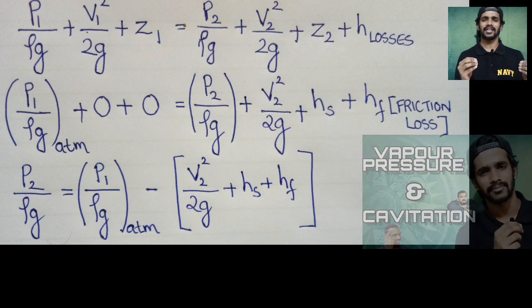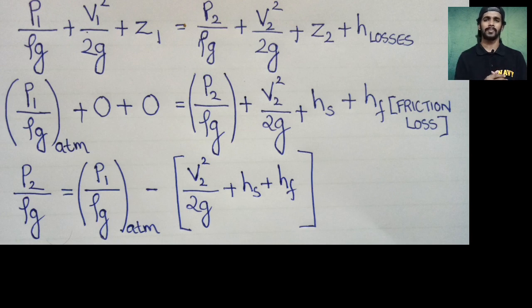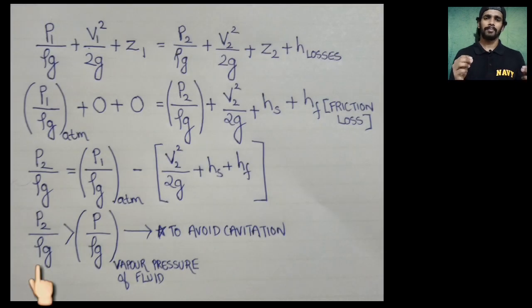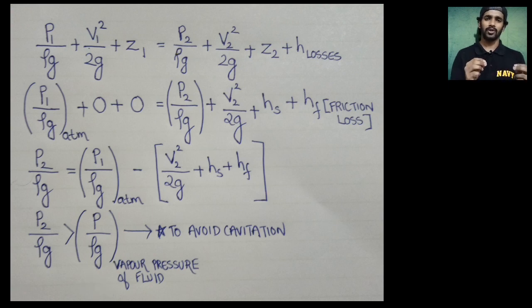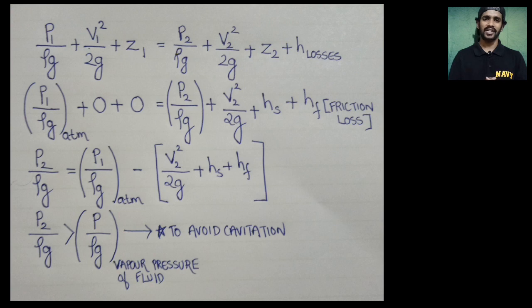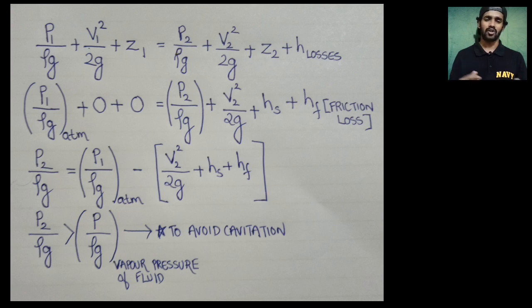As discussed in our cavitation video, the pressure at the eye of the impeller must be less than atmospheric pressure, but it should not be so low that it becomes less than the vapor pressure of the fluid — because if that happens, cavitation will occur. We modify the equation: P2/ρg must always be greater than Pvapor/ρg, the vapor pressure of the fluid. This condition is essential to avoid cavitation.